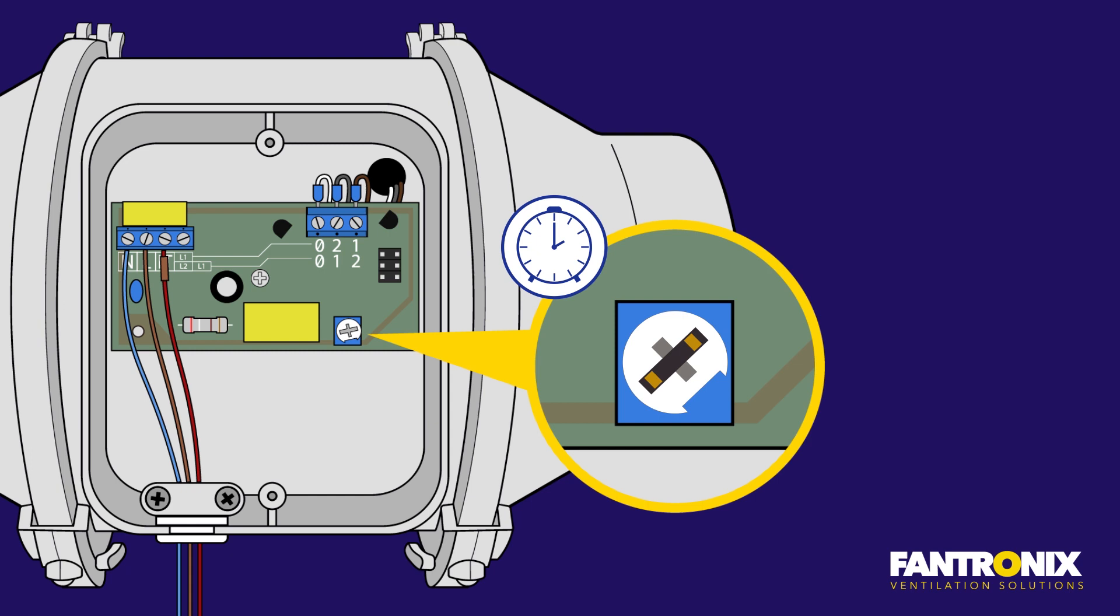The time that it runs on after the activation of the light can be adjusted using the plastic tool provided with the fan. If you turn the potentiometer all the way anti-clockwise, you'll get a two minute run-on. If you turn it all the way clockwise, you'll have a 30 minute run-on, and you can adjust it between those two points to get the timing of your choice.